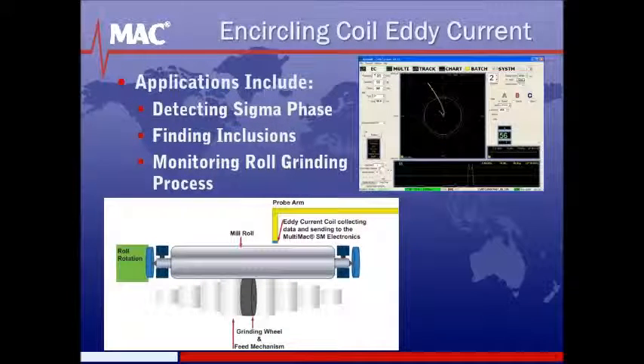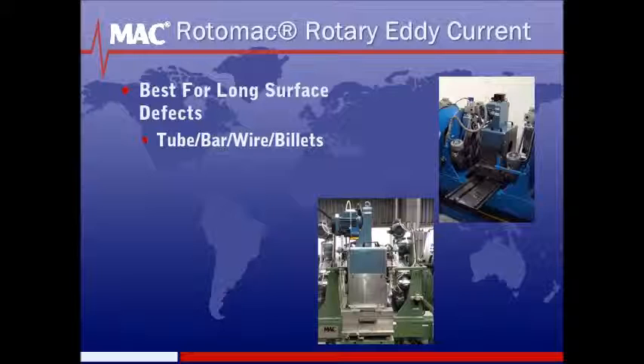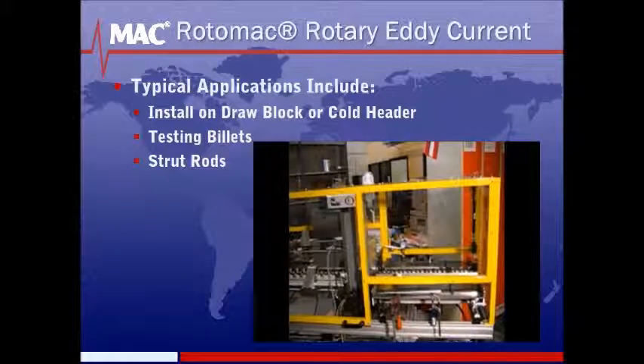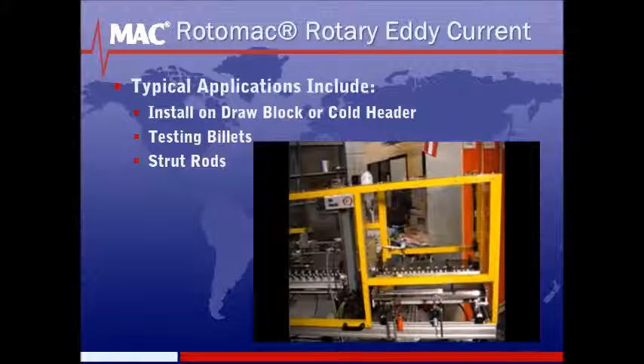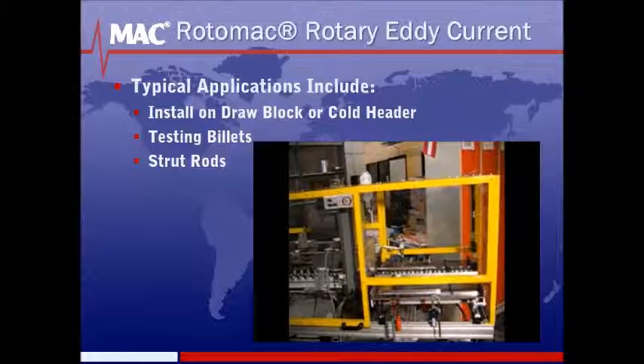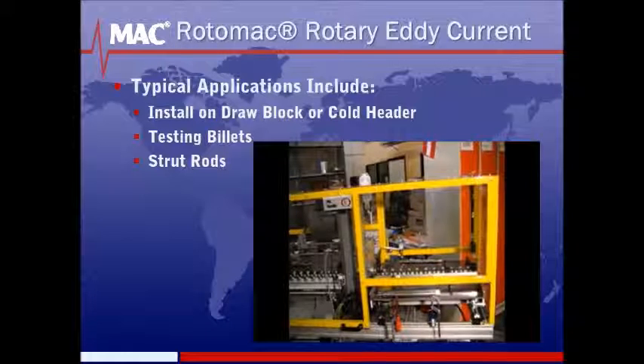Additional applications for eddy current coil systems include testing uniform cross-sectional materials such as squares, rectangles, hex, and round, detecting sigma phase occurrences, finding inclusions, and monitoring roll grinding processes. Typical applications for rotary test sensors are to detect seam-type surface defects in cold-drawn wire or cut-length bar stock. Other applications include inspecting cut lengths like strut rods, usually offline, and testing parts such as small shafts and bearings for longitudinal surface defects.